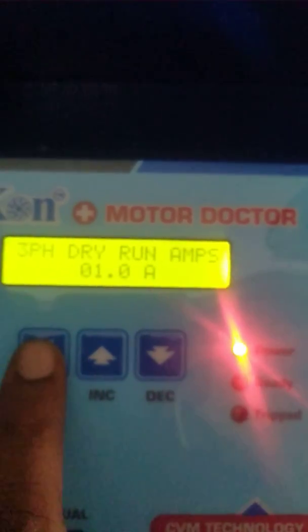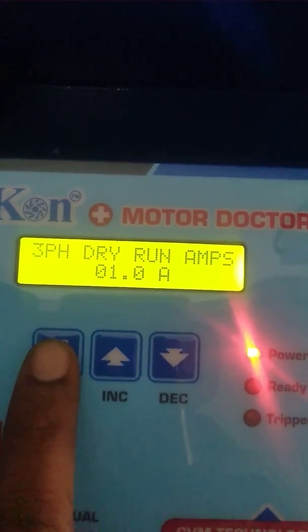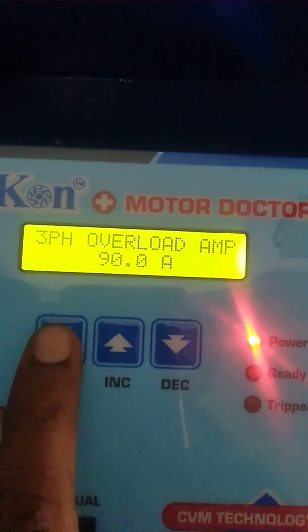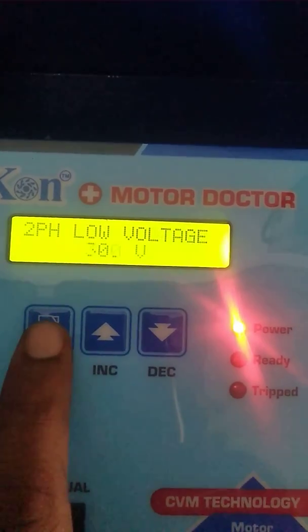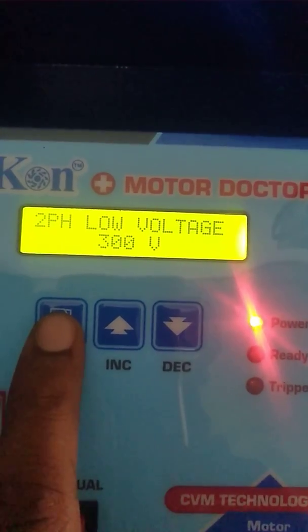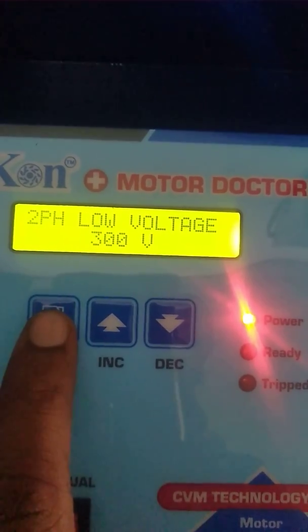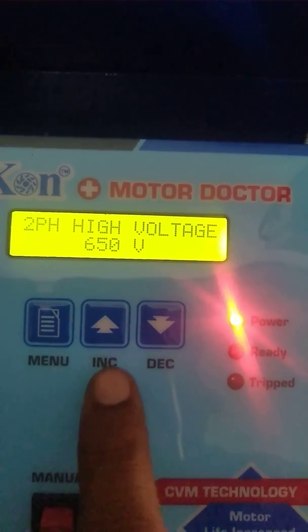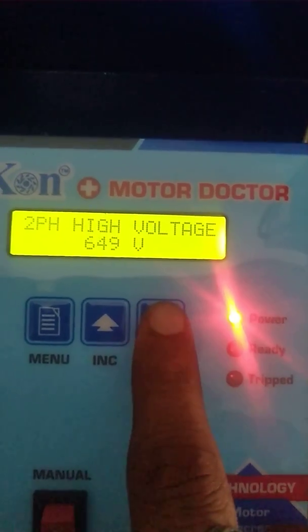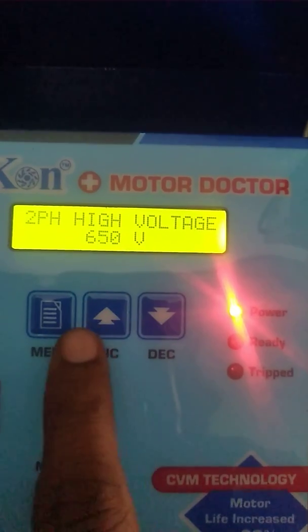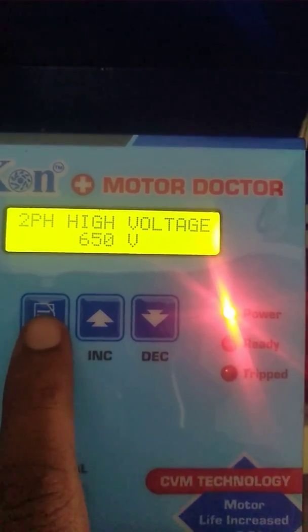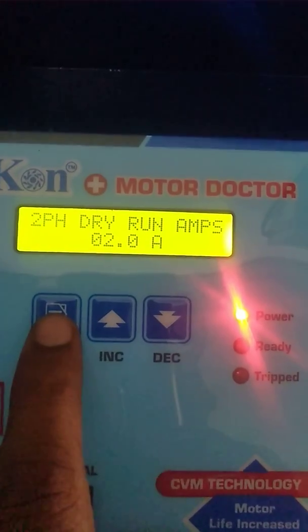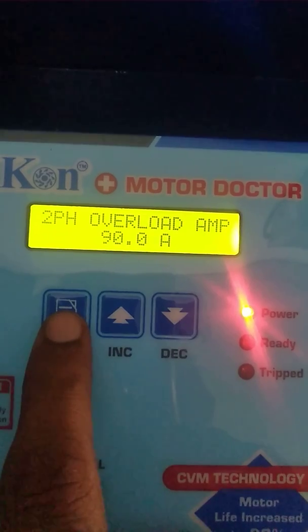Then 3-phase dry-run amps. Then 3-phase overload amps — 90 amps. Then 3-phase to 2-phase low voltage — 300V. Then 3-phase to 2-phase high voltage. These are the increment and decrement buttons — if you want to decrease, press decrement; if you want to increase, press increment. Then 2-phase dry-run amps — 2 amps. Then 2-phase overload amps — 30 amps.